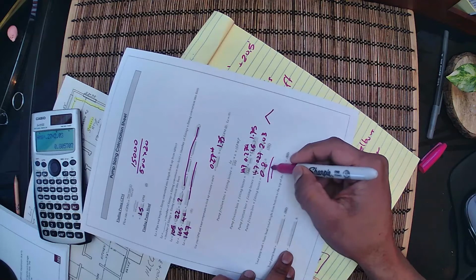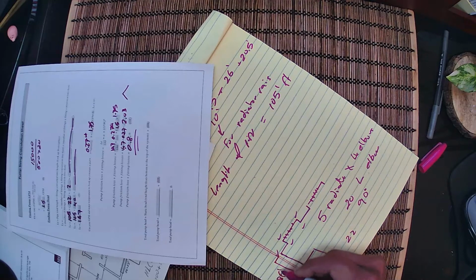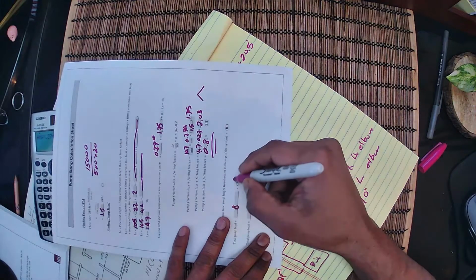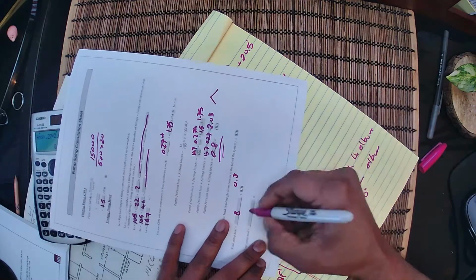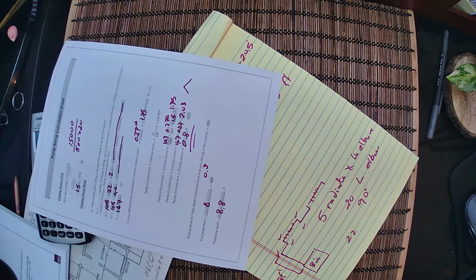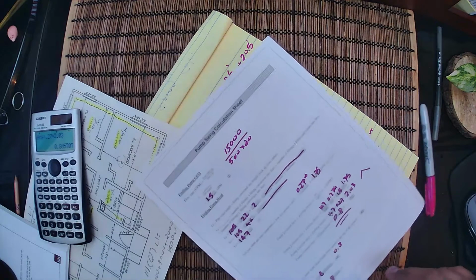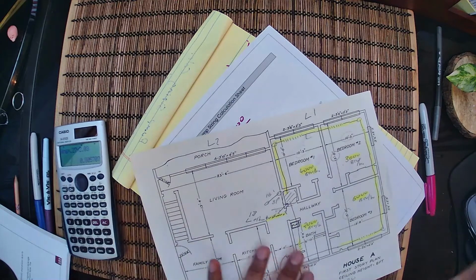So total pump head is going to be this number plus the static, which is the height. So if I look again at my picture here, this is the height from the boiler to the first floor, and I will say it's 8 feet as an average ceiling. So it's going to be 8 feet over here plus this number, which is 0.8. So it's going to be 8.8 feet, and that's going to be the pump head that we need. If we get a pump that's only 8 feet, it's not going to be able to push the fluid around. And again, that was a very, very conservative way to do the calculation.